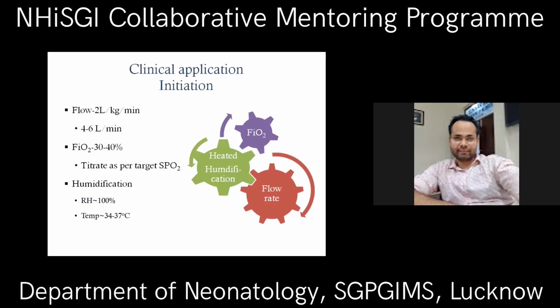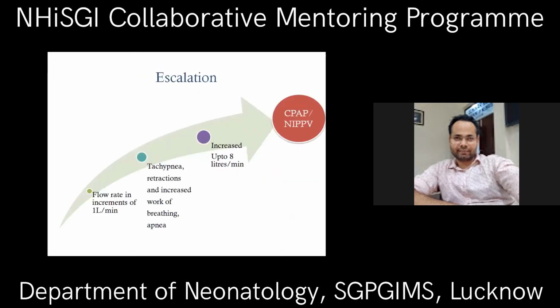For the initiation of HFNC, we should start the flow at 2 liters per kg per minute. That is, we can start at 4 liters per minute. Then FiO2 starting could be 30 to 40%, and we have to target the SpO2 and titrate accordingly. The humidification, relative humidity should be around 100%, and temperature should be between 34 to 37 degrees.